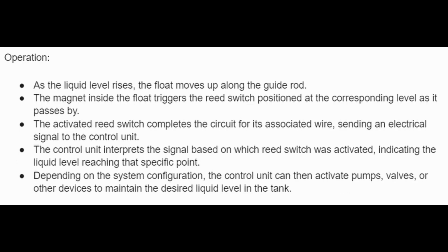Operation. As the liquid level rises, the float moves up along the guide rod. The magnet inside the float triggers the reed switch positioned at the corresponding level as it passes by. The activated reed switch completes the circuit for its associated wire, sending an electrical signal to the control unit. The control unit interprets the signal based on which reed switch was activated, indicating the liquid level reaching that specific point. Depending on the system configuration, the control unit can then activate pumps, valves, or other devices to maintain the desired liquid level in the tank.